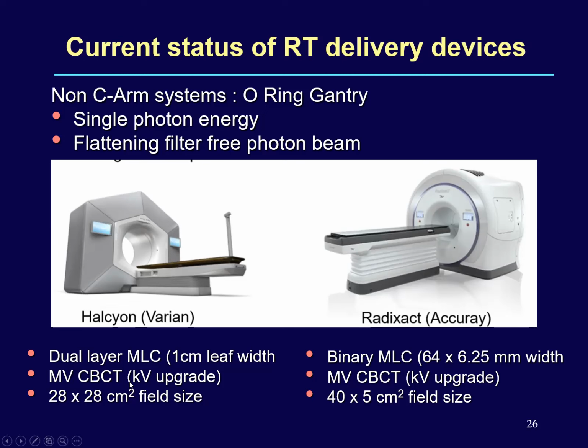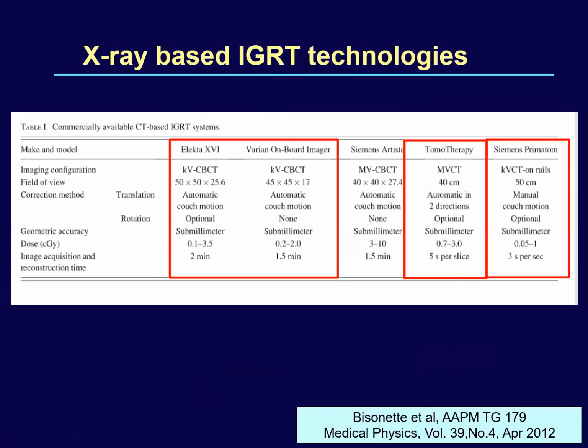This will help for inter- and intrafractional motion management later. But for this Accuray equipment, they use a binary MLC, and it produces an MVCBCT and always uses a narrow fan beam geometry for producing the CBCT. Looking at this slide, all these technologies, whether done through a fan beam or a cone beam, from commercially available systems like Varian, Elekta or Siemens, were able to correct automatically translational and some rotational errors, and all of them offered sub-millimeter accuracy.